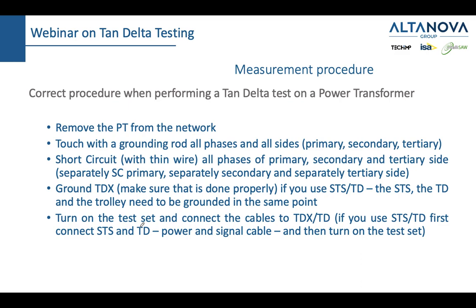Now, the first thing you need to do when you're doing a tan delta test is to remove that power transformer from the network. You simply open the circuit breaker, you open the disconnectors so that you are the one who is generating voltage and current. The next step is usually prescribed by all the utilities.